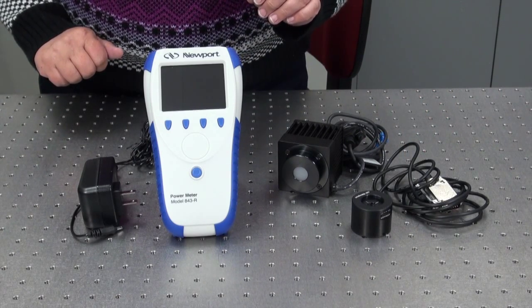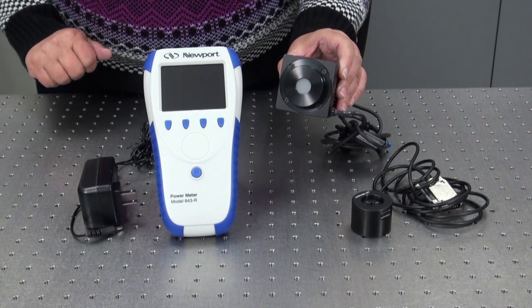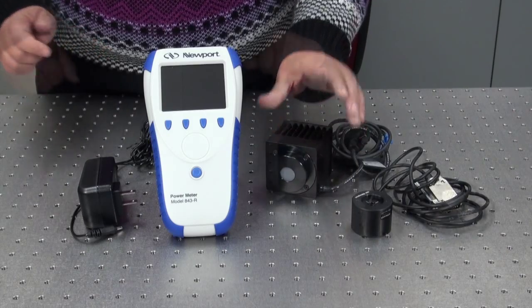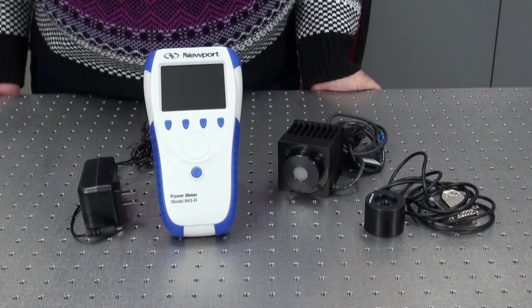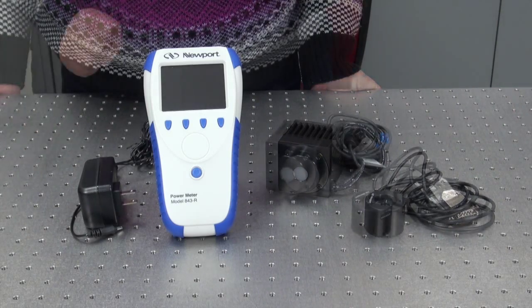The 843-R is also compatible with the new 919P series thermopile detectors. The 843-R is not compatible with the 818P series thermopile or the 818E series pyroelectric detectors.